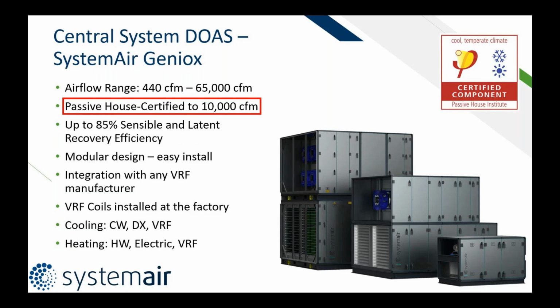That's a PHI certified unit. Truly a certified component, has that badge right there. So that's technically up to the housing size 27. So yeah, you can basically consider up to 10,000 CFM. We can deliver a truly Passive House certified unit. That unit we can provide with up to 85% sensible and latent recovery efficiency.